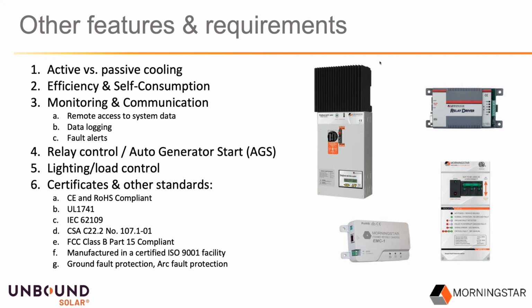For example, if this system is getting permitted and it's subject to the National Electric Code, that's going to be a different set of requirements, where you're looking at things like arc fault protection and ground fault protection, versus something at a remote site that might not be subject to all those same requirements, but you still want some basic CE compliance, maybe a UL listing just for good measure.